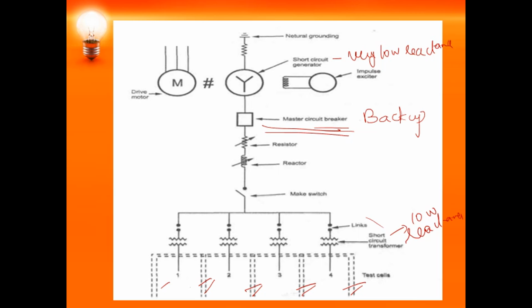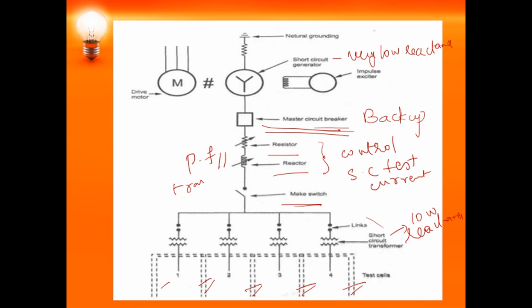Next is the make switch, or the making switch. What is the making switch? If you close this, the current flows through the short circuit transformer to the circuit breaker under test. Next come the reactors and resistors. These resistors and reactors are connected over here to control the short circuit test current. They will also control the power factor as well as the transient recovery voltage. So this is the laboratory setup of your circuit breaker testing.